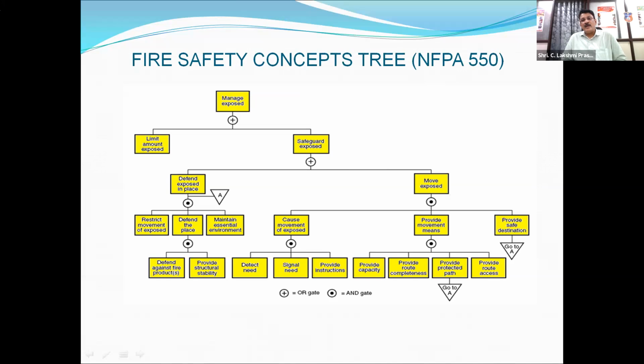Nowadays in Hyderabad, we are permitting buildings of about 200 or 250 meters. People are coming with proposals following various norms and conditions, and we are issuing these permissions. In such cases, people going outside the building is not easy. So refuge areas have to be provided at regular intervals, every 15 meters or 5 floors. There should be an area of safe refuge where occupants can protect themselves and stay for some time until the fire conditions become normal, or until they are rescued by the fire department. A refuge area is relatively protected; a staircase that is enclosed, pressurized, and provided with a fire door can also be taken as a place of relative safety.